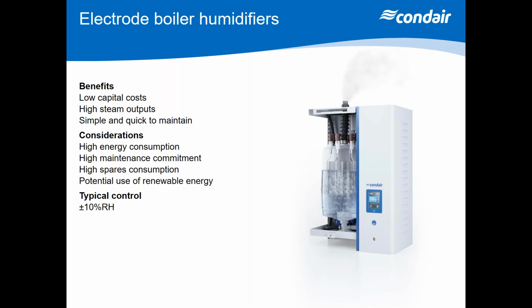They knew that hard water was the issue, so they installed a water softener. Now, a base exchange water softener is going to take the calcium out, but it replaces it with sodium. And that does a couple of things. Firstly, softened water foams at high temperature. So that gives a false reading on water level, so your control goes out. And also, it's corrosive. It eats the electrodes. And indeed, we're not taking any minerals out, we're just replacing them with a different kind of mineral. So that didn't help them. Softened water, not perfect for electrode boiler.